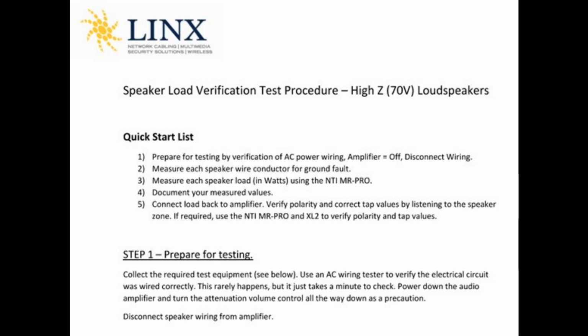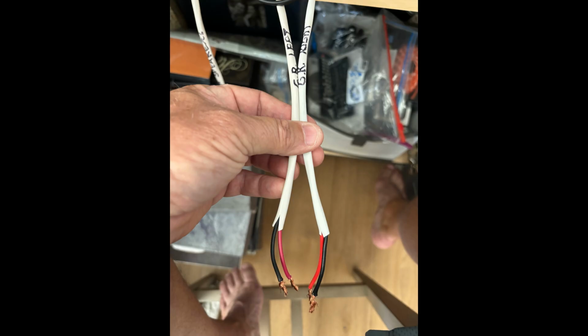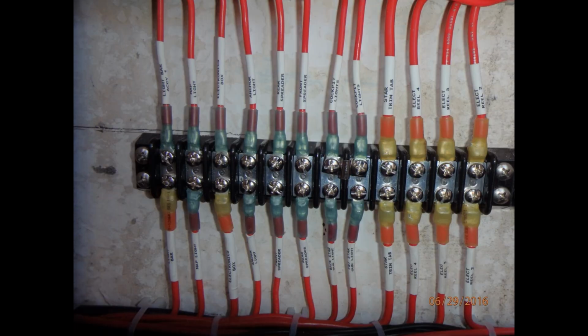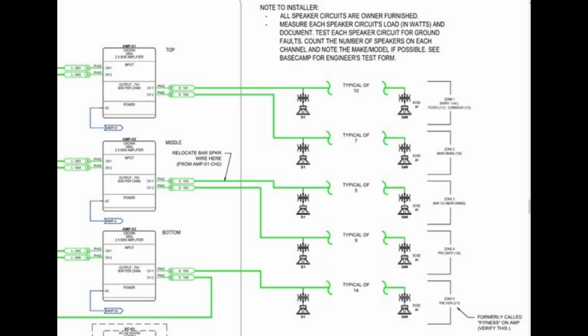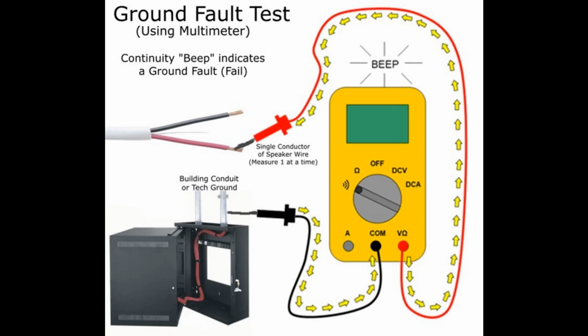Now let's get started with the speaker load verification test procedure. The first thing to do is disconnect the speaker wires from the amplifier, and verify the speaker labels match the test documentation and system drawings. The first test is called the ground fault test, where we can find out if there has been any damage to the speaker cable during installation.